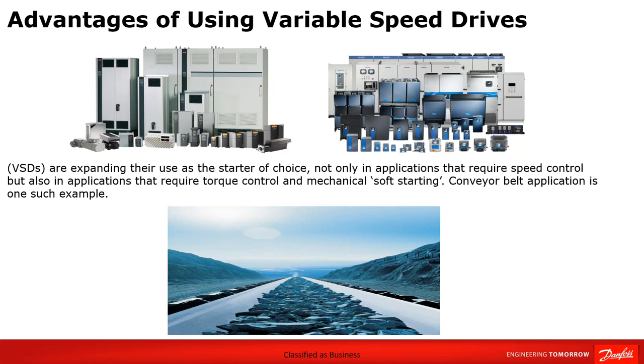Now, variable speed drives are actually becoming the starter of choice. And it's not only in applications that require speed control, but also in those applications that require torque control. And you'll see that as we go through the presentation. Mechanical soft starting in a conveyor belt application would be one such example. So smoothly controlling the acceleration and deceleration of long conveyors reduces mechanical stress through all the drivetrain components and within the conveyor belt itself.